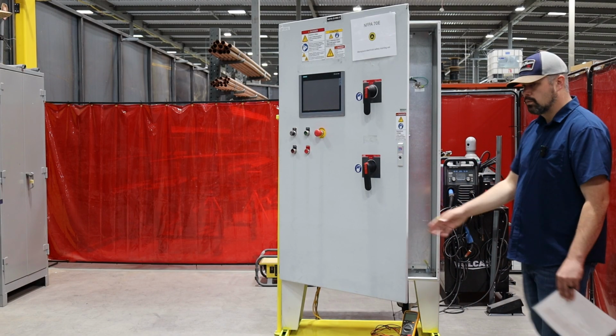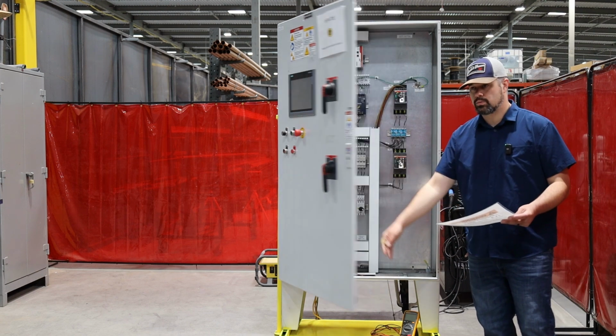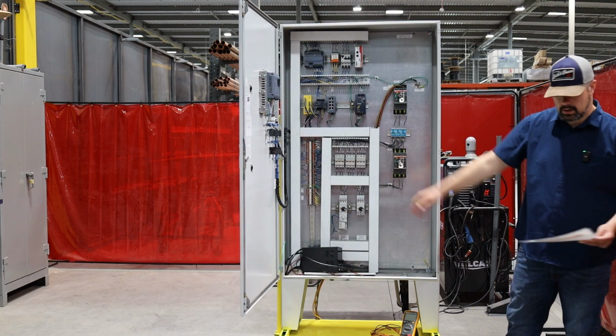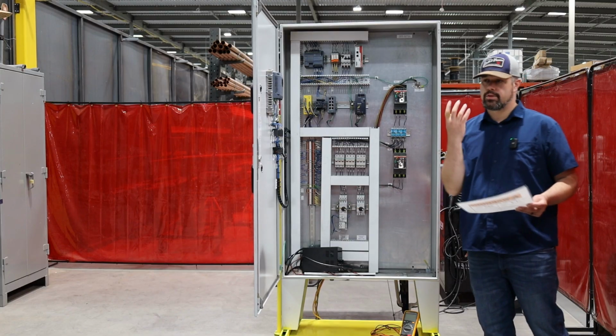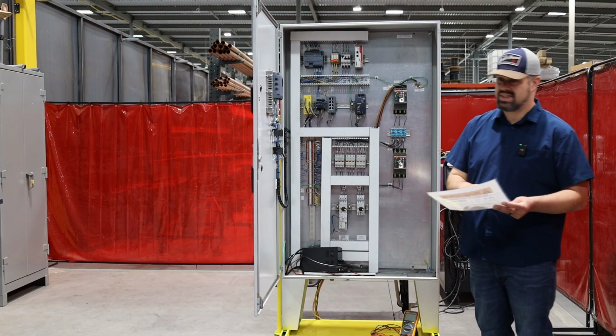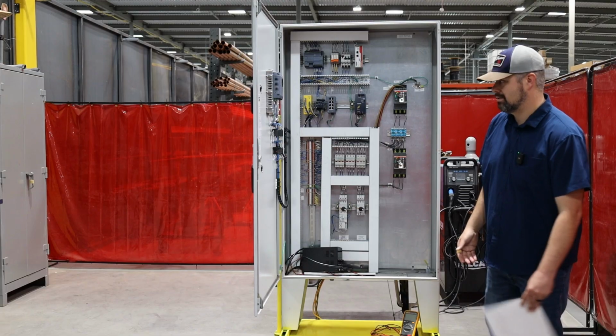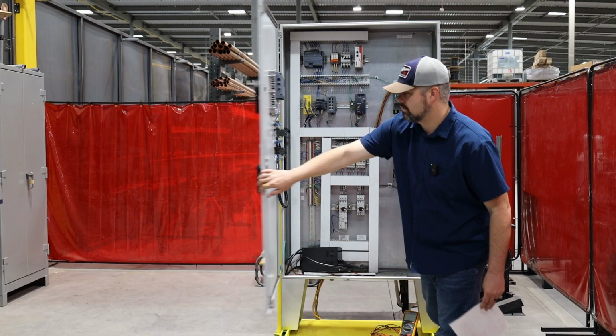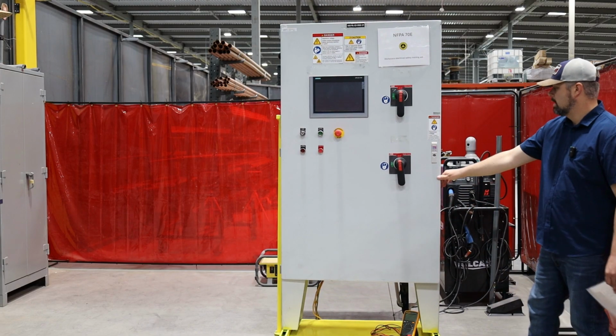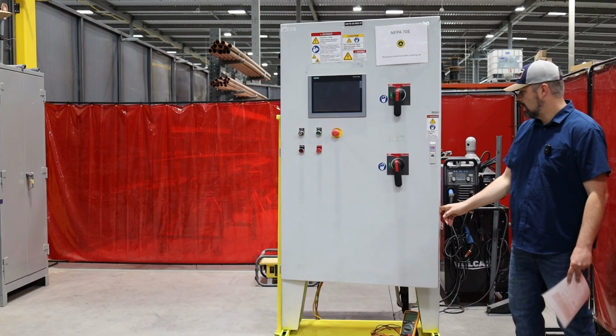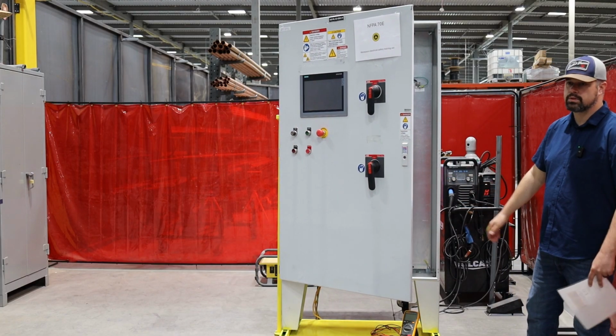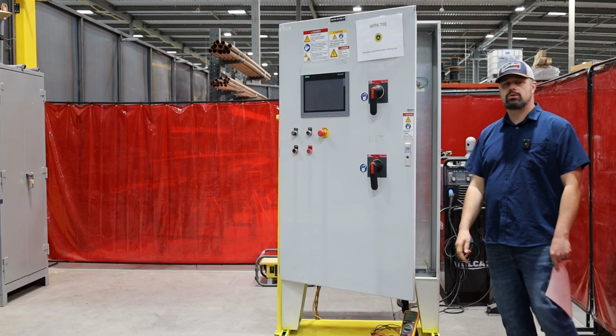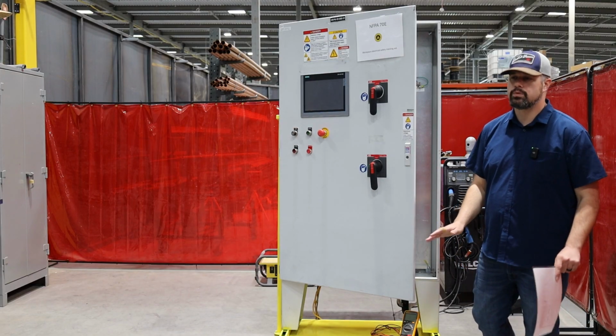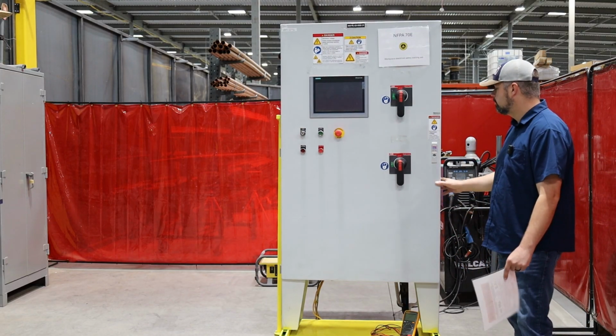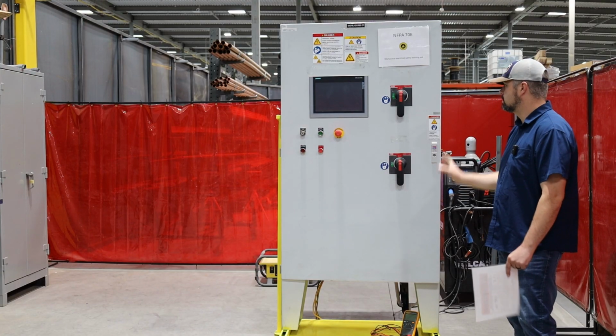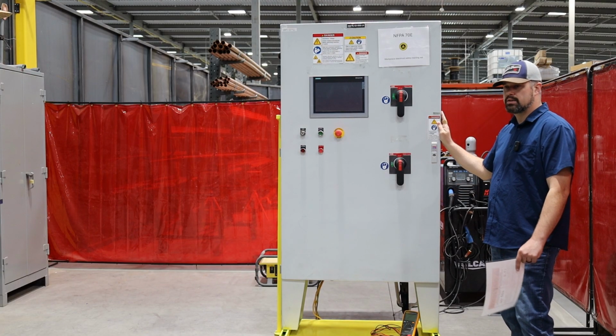Okay, so we already called it out. We've got our barrier, so we're good there. We've got our 42-inch barrier. We did that before we opened the door. We've got on the appropriate PPE we need to be within any of the boundary, even if we're not going to be within the boundary. I mean, technically speaking, I could probably open this cabinet and maintain 18 inches away from an exposed conductor, but we can't do that with 100% confidence, right? I don't know exactly where there's an exposed conductor when I open this panel.